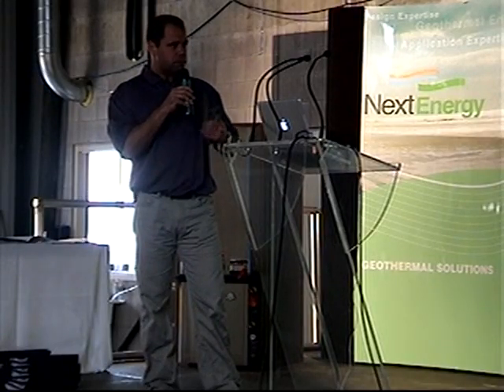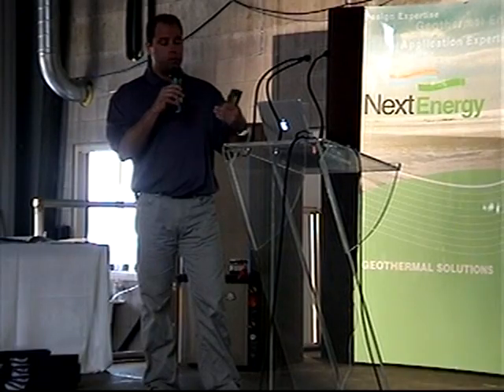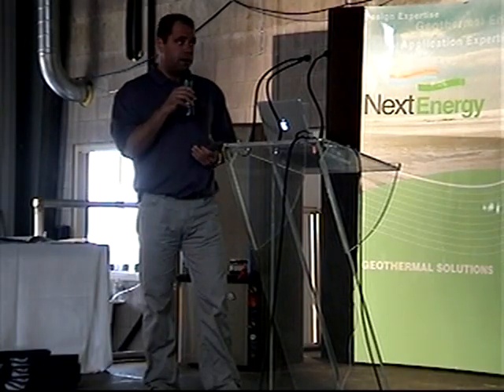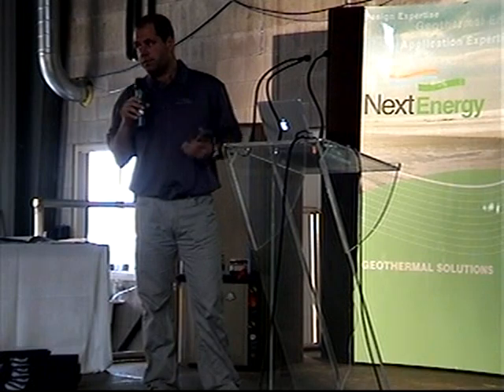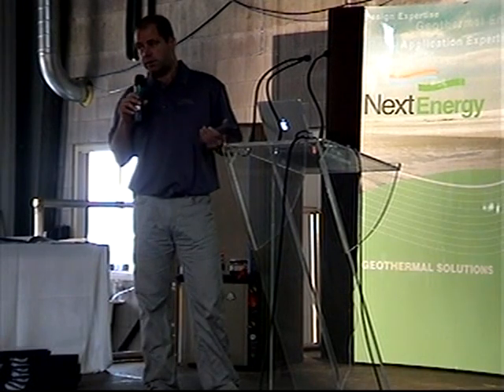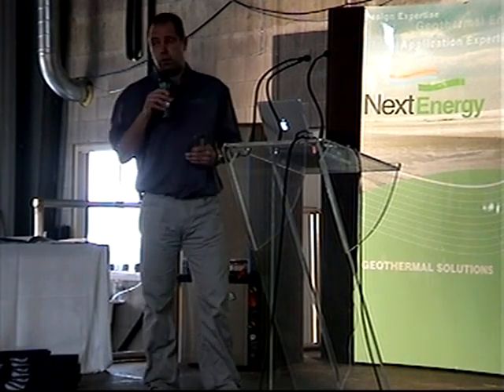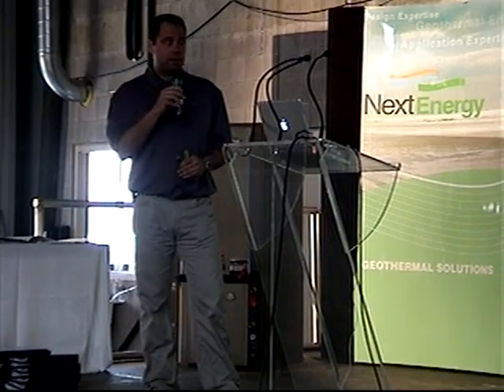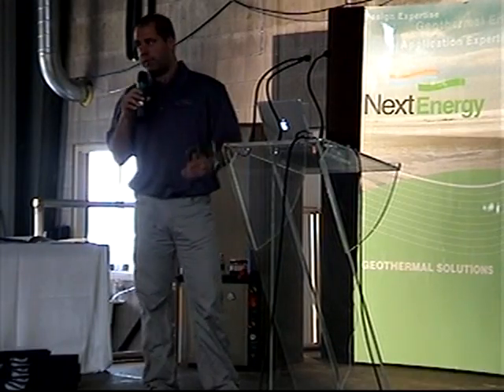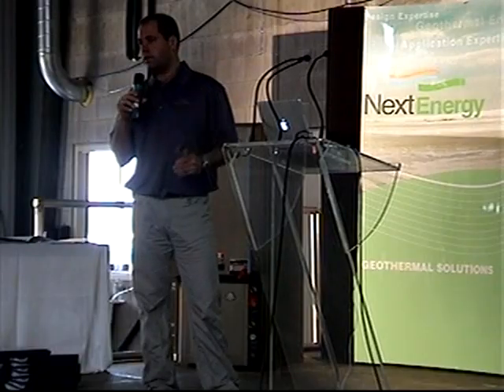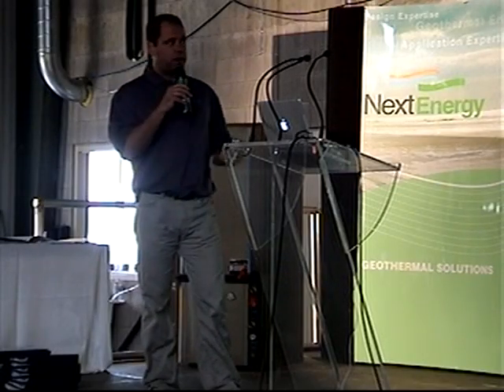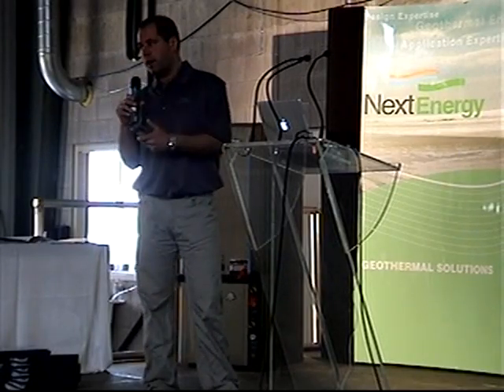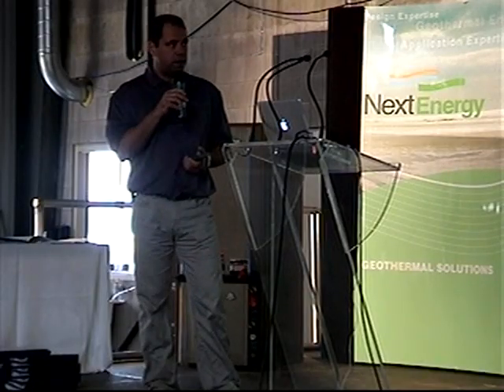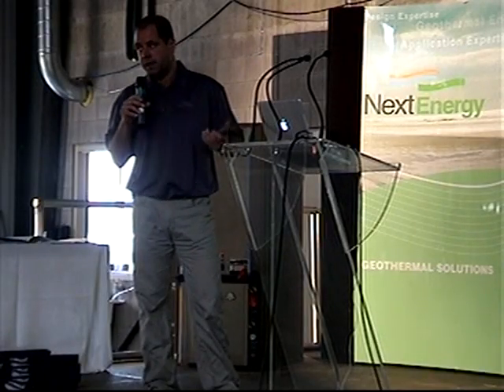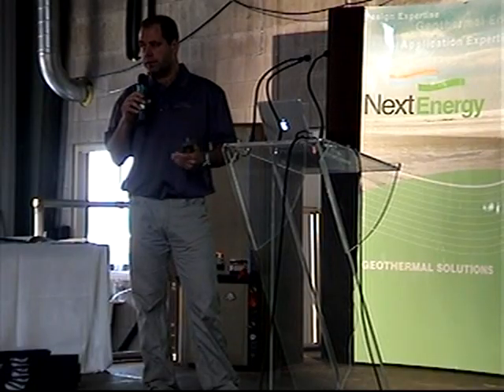And an indication of poor subcooling could be if a unit's low in charge, you'll have very low subcooling, possibly no subcooling. If a unit's overcharged, if you put too much gas in it, that means you've flooded the condenser with liquid and you're going to have way too much subcooling. So all those charts are in your IOM books, manufacturer specs on temperatures, subcooling, superheat.